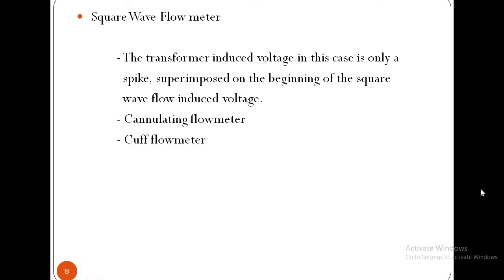Also, it is easier to control the magnitude and wave shape of the energizing current in the case of a square wave system. The transformer induced voltage in this case is only a spike superimposed on the beginning of the square wave flow induced voltage. Separation of these two voltages becomes easier as the amplifier can be gated only for a very short period. The square wave is amplitude modulated by the variation in blood flow and requires to be demodulated before it can be fed to a recorder.